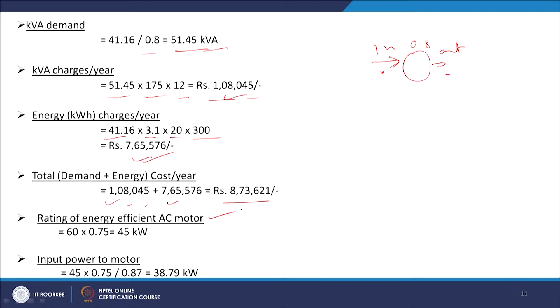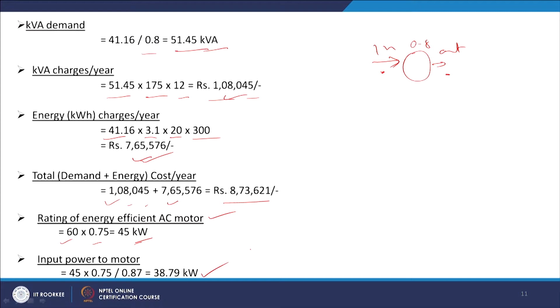If we use the energy efficient motor, then the rating of the energy efficient AC motor is also 60 HP, so 60 HP is equivalent to 60 into 0.75, that is 45 kilowatt, and its efficiency is higher, that is 87%. So, the input power to the motor will be 45 into 0.75, that is what it is actually using, but as it is 87% efficient, it has to be divided by 0.87. So, this is 38.79 kilowatt, the input power to the motor.